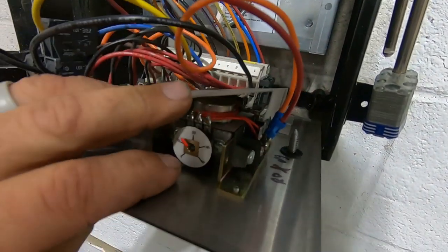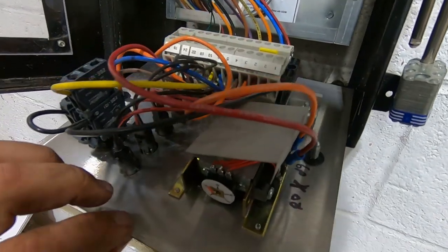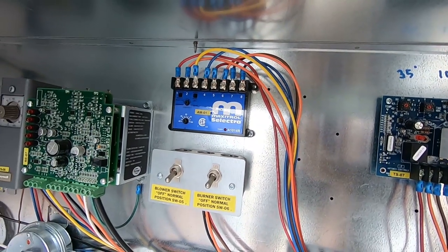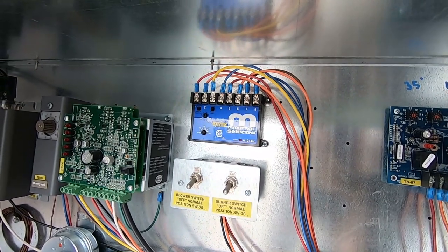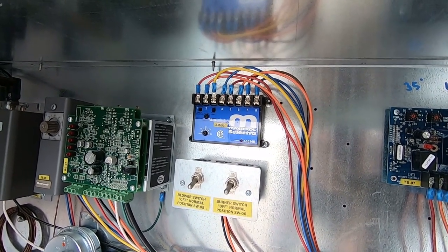Checked it back at the Maxitrol valve, so I don't have any resistance in the wire causing any issues. When you unhook one and two, which is from the control on the inside, and check that, I had 10k there.